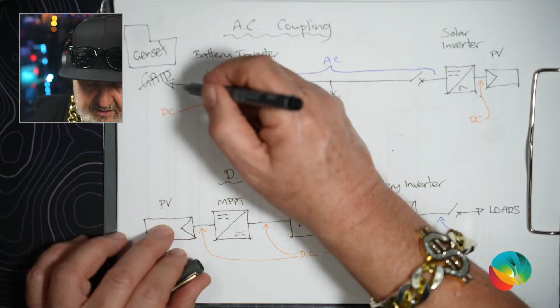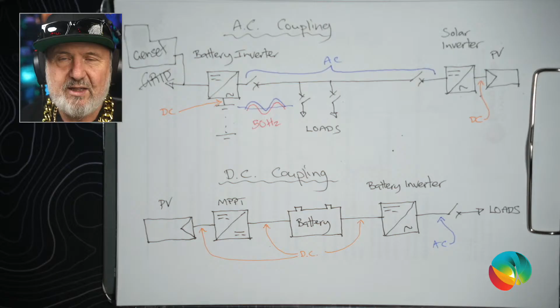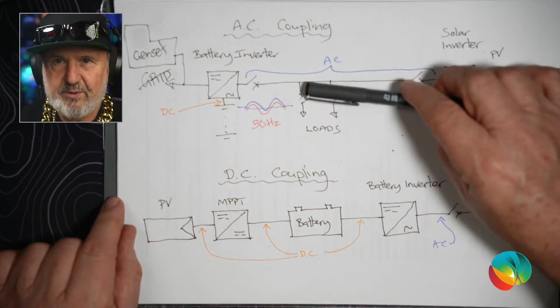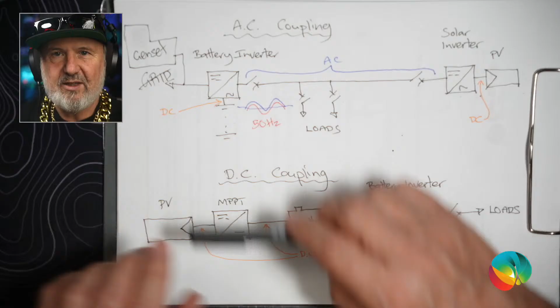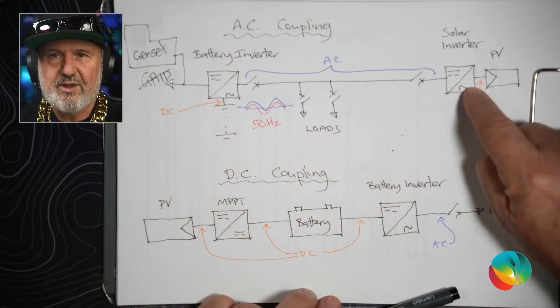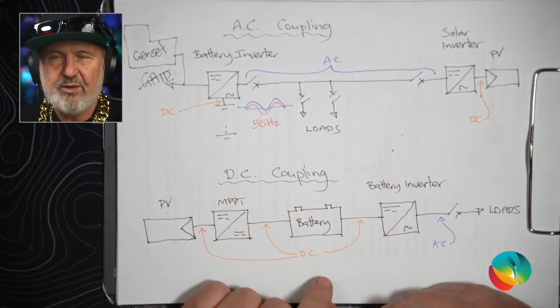But if you don't have a grid, so if we cross that out and say it's a generating set, and typically that'll be a diesel or petrol generating set. I've said this many times, it sounds a bit funny, but you can't export electricity to a generating set and make diesel, right? It's a one-way device. So we now have a problem. If we're supplying the loads, and the battery's full, it can't go back to the generating set, so we have to curtail generation. So we have to somehow control this inverter so it doesn't produce more than what's required by the combination of loads and the battery. And that can be done in two ways.